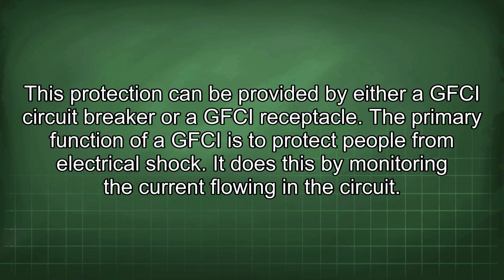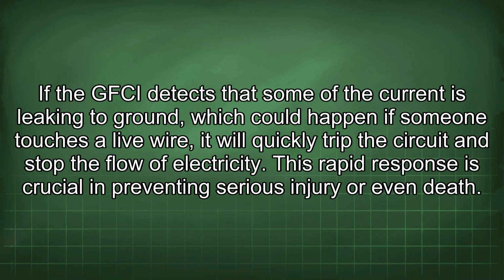The primary function of a GFCI is to protect people from electrical shock. It does this by monitoring the current flowing in the circuit. If the GFCI detects that some of the current is leaking to ground, which could happen if someone touches a live wire, it will quickly trip the circuit and stop the flow of electricity. This rapid response is crucial in preventing serious injury or even death.